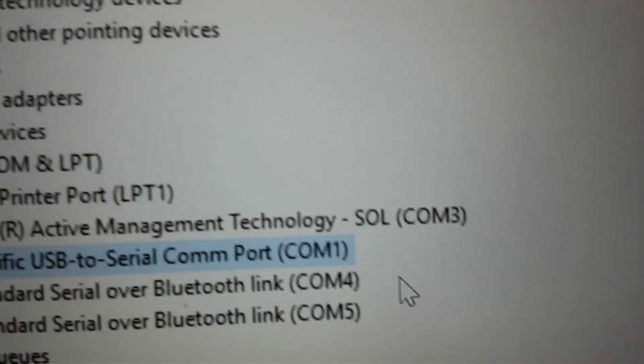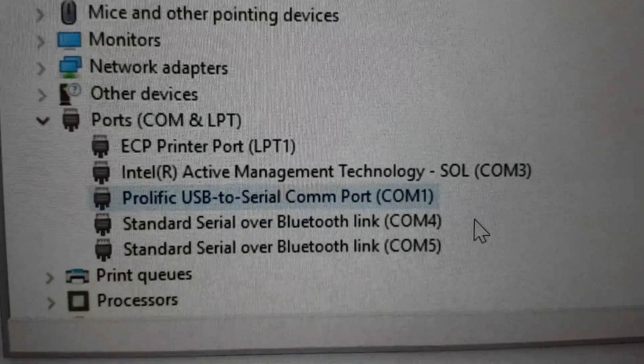I have had no issues running this type of connection and it seems to work very well with both DX's as well as all of the N2 devices. As you saw in the video, I am running the GX9100 software as well as HVAC Pro on my Windows 10 machine. Following these steps you can set up your hardware to communicate with the USB to serial converter — you just got to remember to change it to the correct port. The older software only recognizes two ports when there are many more available on a lot of modern machines through USB.